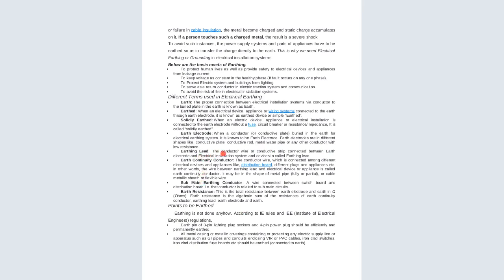What is the earthing lead? The conductor wire or conductive strip connected between the earth and the electrical installation system and devices is called the earthing lead. Then there is the earth continuity conductor. This is the conductor wire connected among different electrical devices and appliances, like the distribution board and the different plugs and appliances.